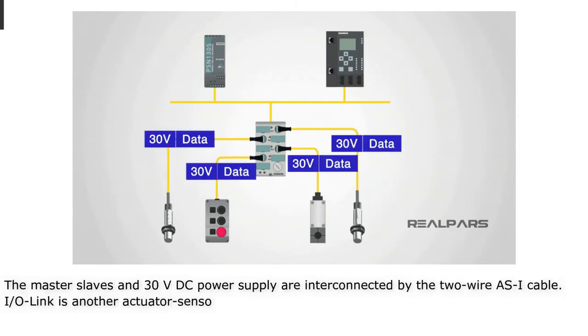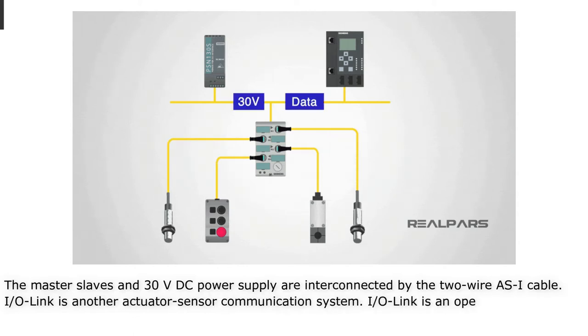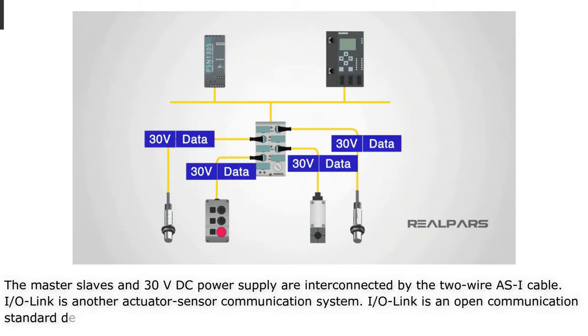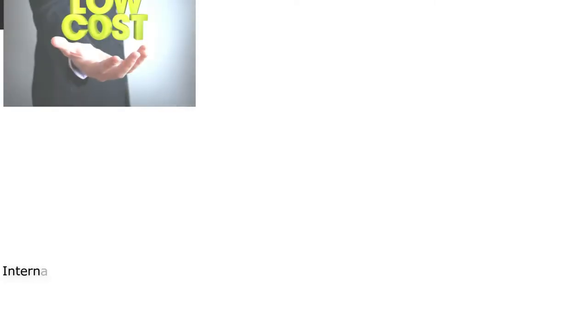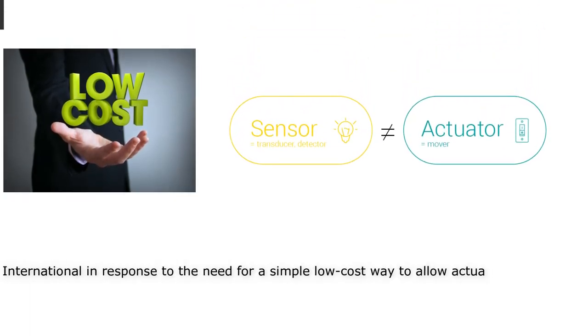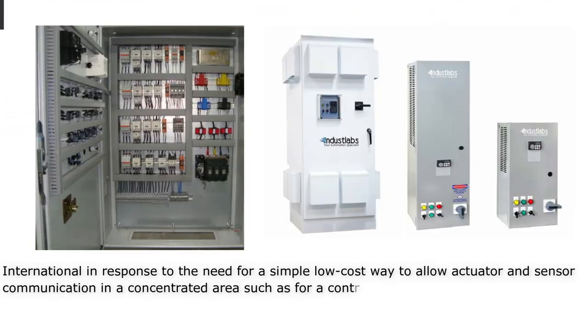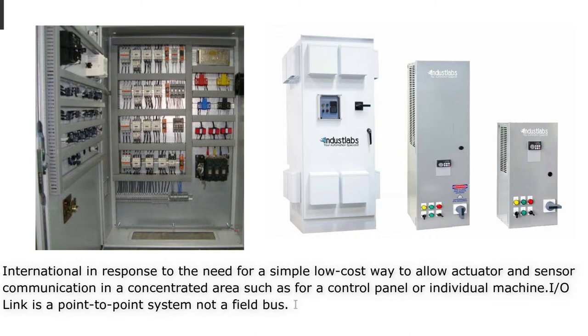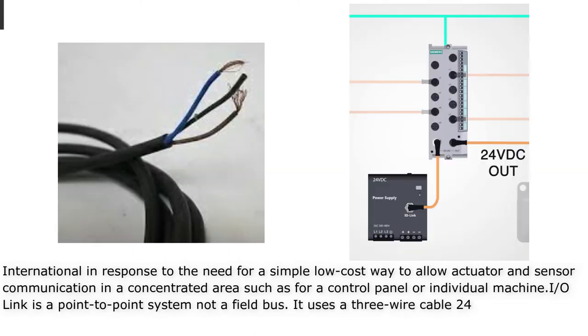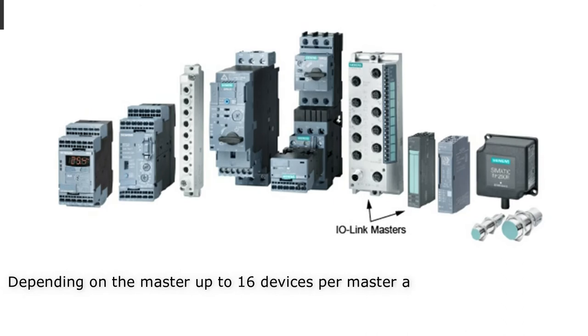IO-Link is another actuator-sensor communication system. IO-Link is an open communication standard developed by the IO-Link research group of Profibus and Profinet International, in response to the need for a simple, low-cost way to allow actuator and sensor communication in a concentrated area such as a control panel or individual machine. IO-Link is a point-to-point system, not a fieldbus. It uses a three-wire cable, 24 VDC power supply, and an IO-Link master, with up to 16 devices per master allowed.